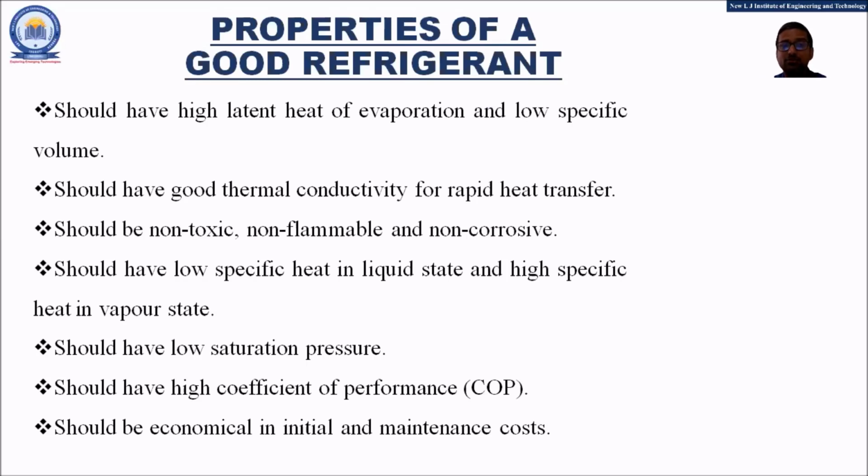A good refrigerant should have a high latent heat of evaporation and low specific volume. Latent heat is that type of heat which is responsible for the phase change. Also, a good refrigerant should have maximum thermal conductivity in order to ensure rapid heat transfer. It should be non-corrosive, non-flammable and non-toxic because the refrigerant will be flowing through the pipes. So it should be non-toxic, non-flammable as well as non-corrosive.